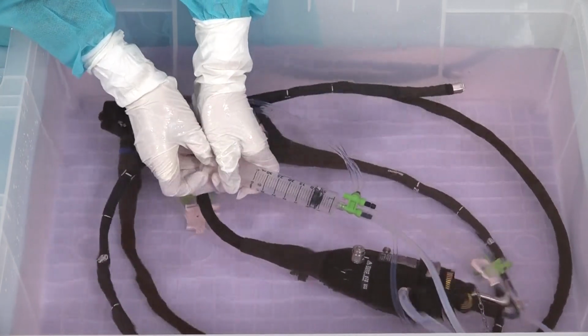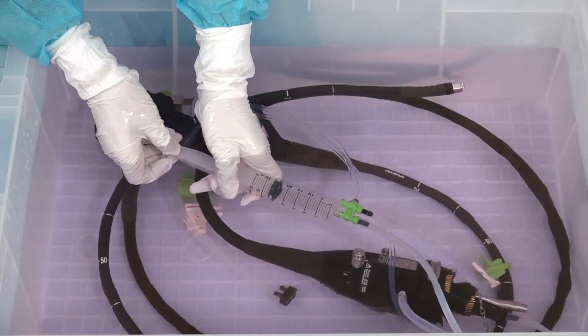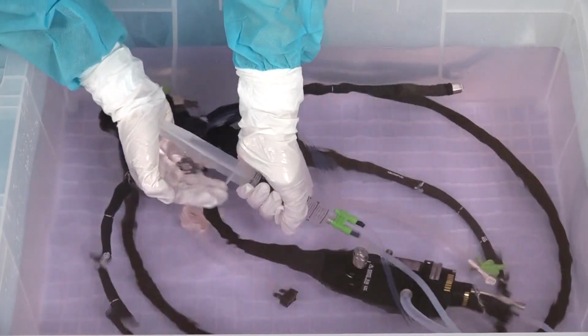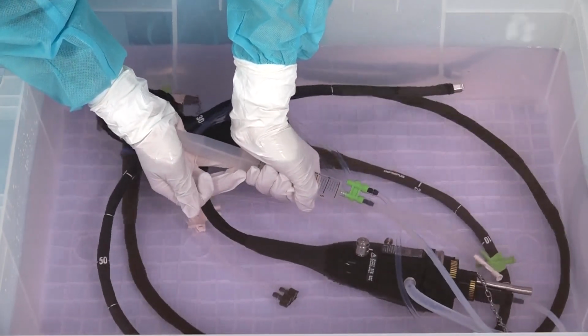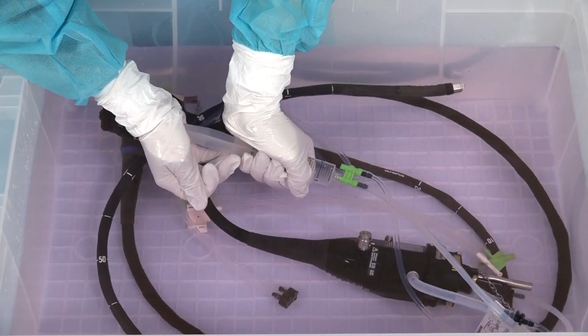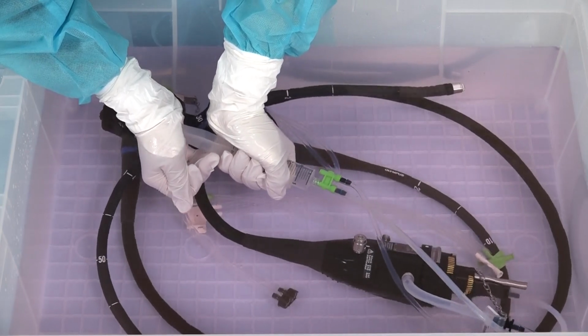Confirm that no air bubbles exit the distal end during the last flush. If air bubbles still exist during the 6th flush, flush the channel with the disinfectant solution until no air bubbles exit.